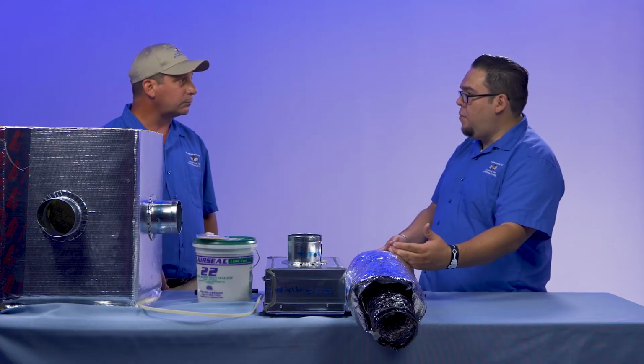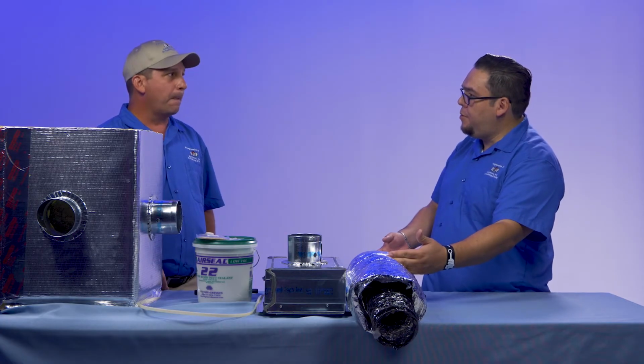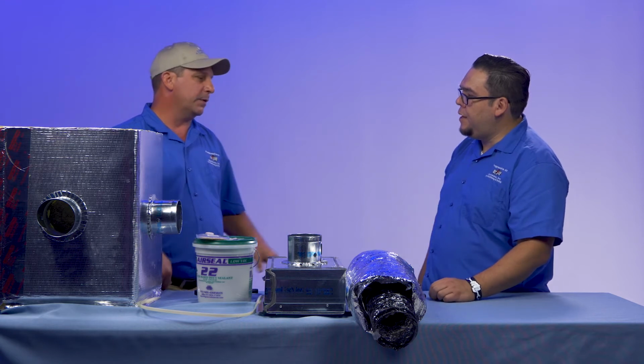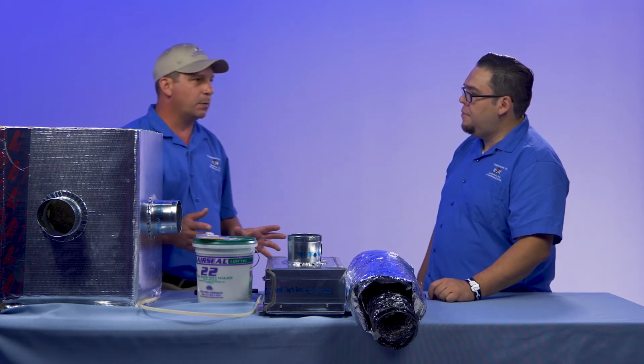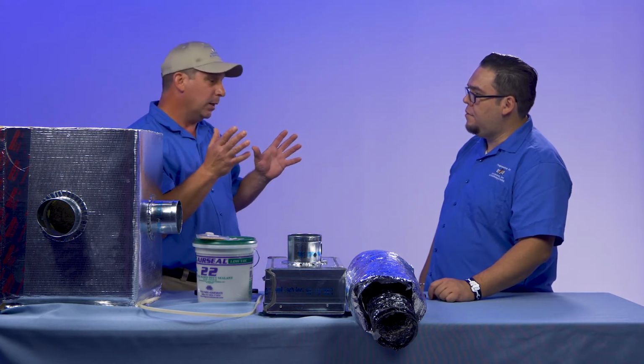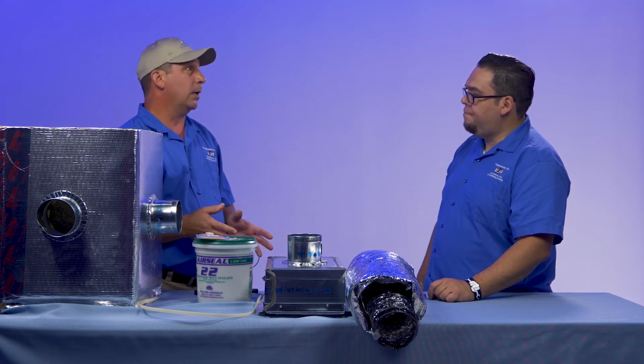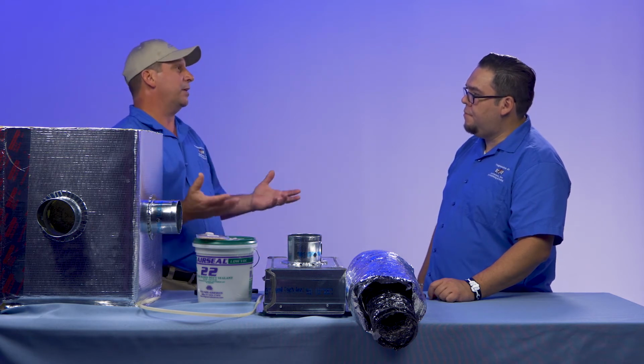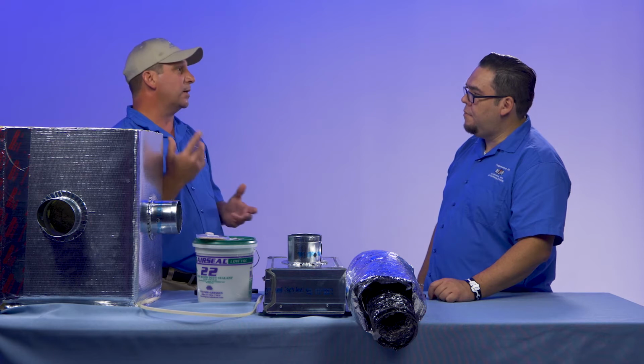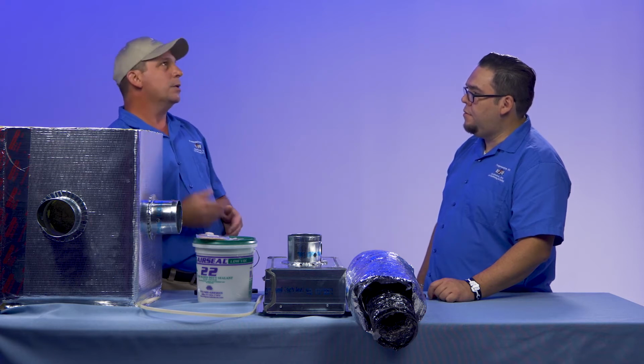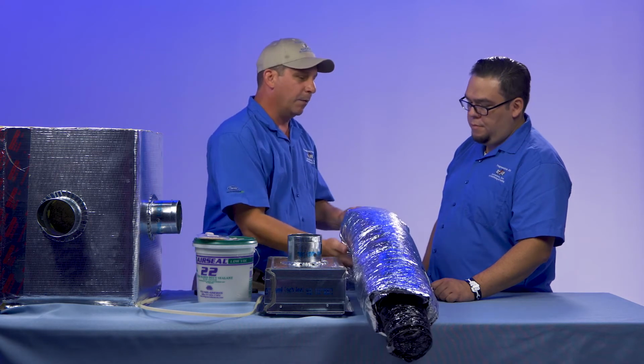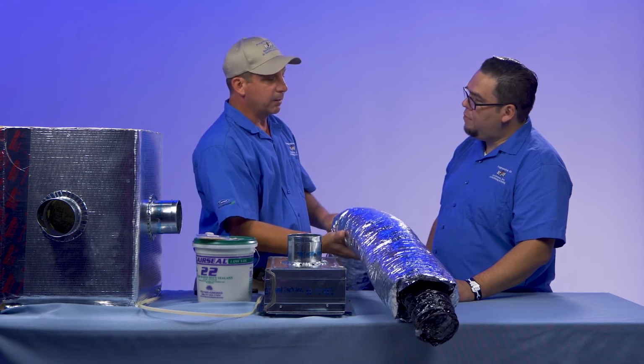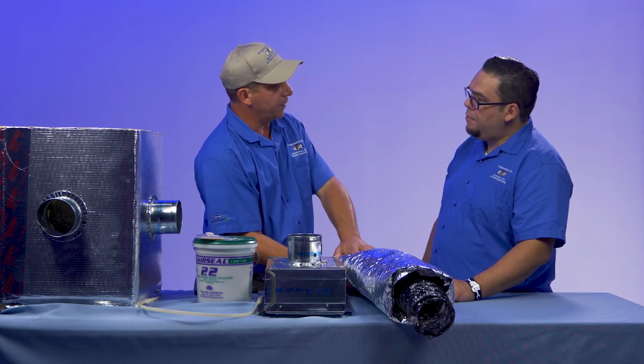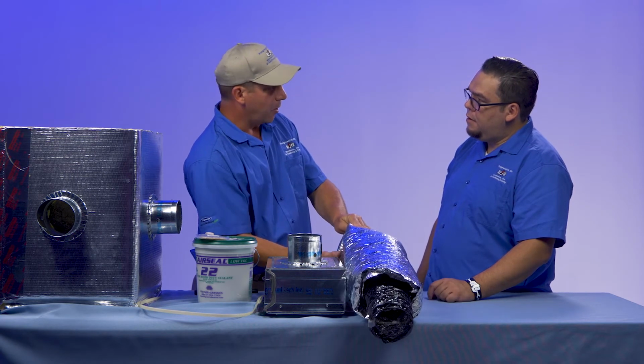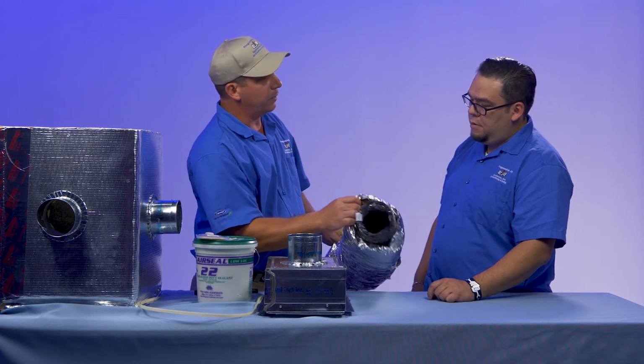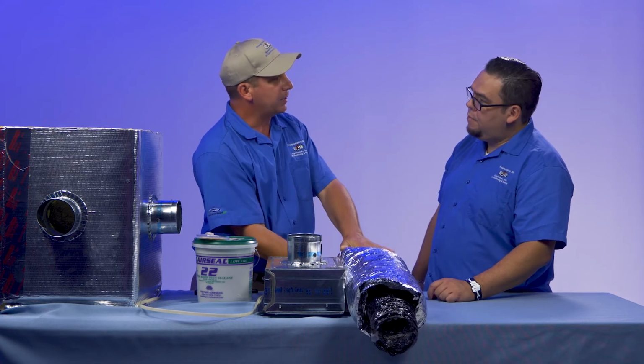And if you have had a sweating issue, is it necessarily a replacement as well? Absolutely. I find a lot of the time where homeowners have set something down on their ductwork, and months later, even a year later, they'll see little water spots up in their ceiling. They go, well, what's that? So I get up there and I find that on the bottom of here, because it's pushed down so much on the duct, the R value of that inner liner has been lost.